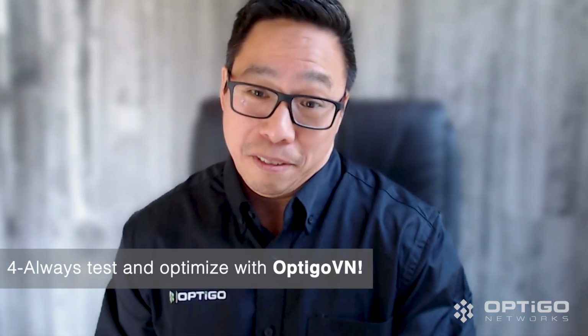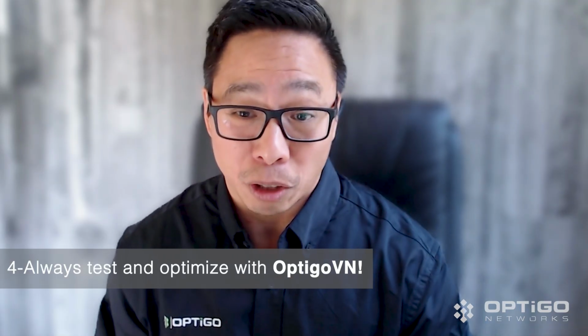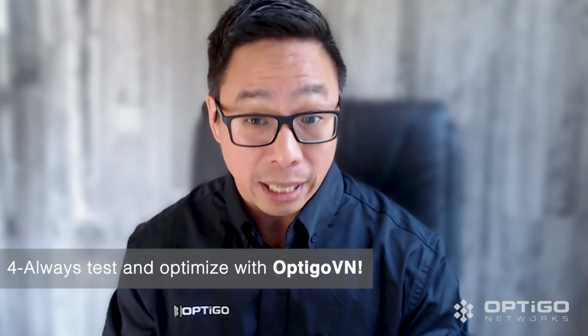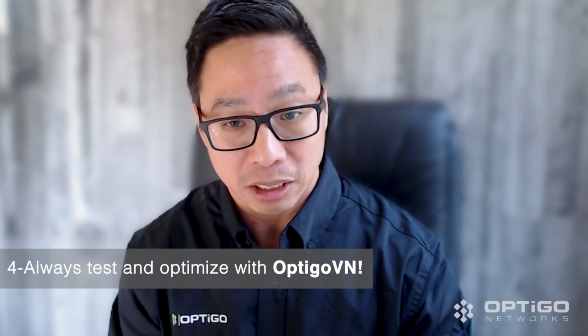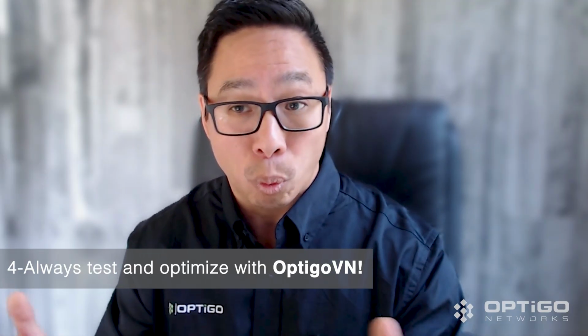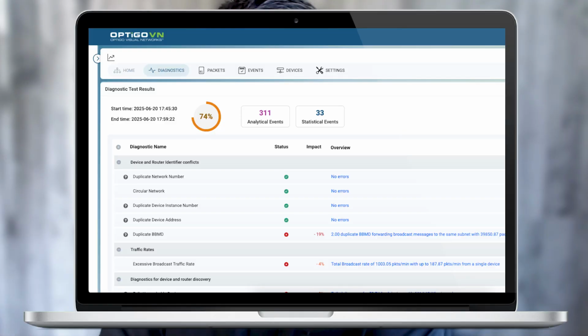BBMDs are quite difficult to troubleshoot. Excessive broadcast is one of the primary reasons why building automation systems don't operate at the desired performance. So if I may plug in here, use a software like Optigo Visual Networks to analyze how much BACnet broadcast message you have, and also where those messages are coming from. Perhaps you have a duplicate BBMD, and you can quickly identify those duplications and be able to eliminate it with the use of Optigo Visual Networks.